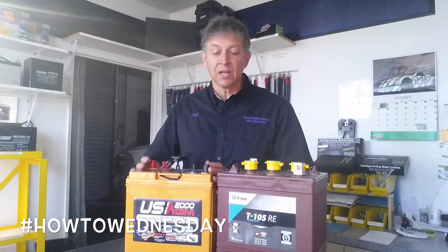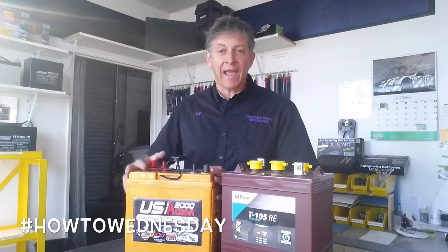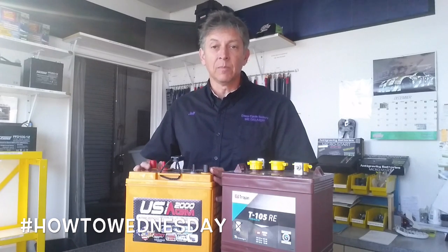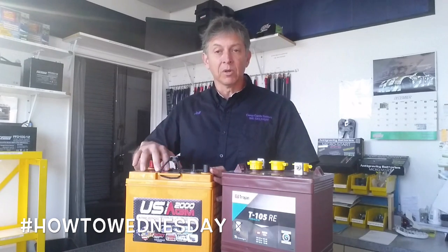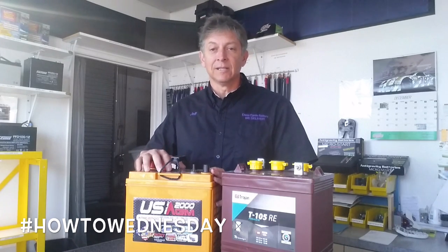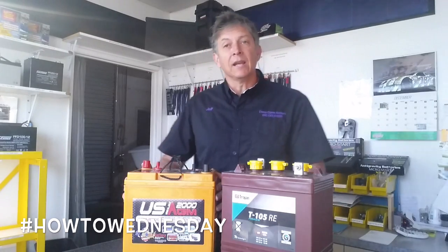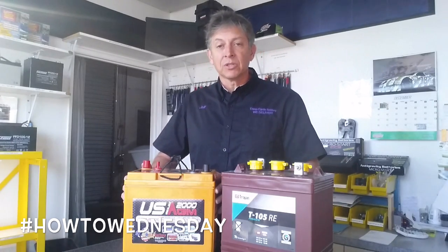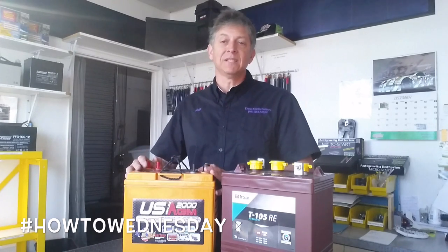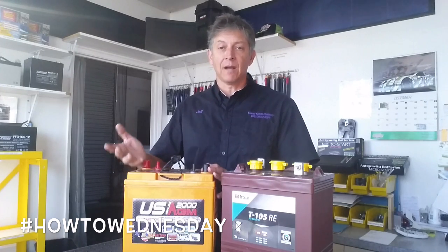If I were to discharge these batteries in 1 hour, I would potentially have less amps available. To give you an explanation of how to calculate what these numbers mean, let's take the 210 amp hour AGM battery: 210 amp hours divided by the 20-hour rate of discharge gives you about 10.5 amps per hour of available power until the battery goes down to zero.